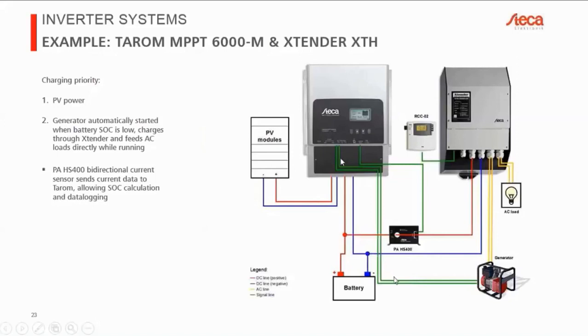Now, this generator can either be controlled by the charge controller in this case, or you can also control it by the Xtender, regardless. Either one of the two can give the generator a signal to start running when the battery is low, for example. And then finally, we also have a current sensor in the system, which can measure up to 400 amps. The reason we have the current sensor is so that we can see how much energy is flowing into the inverter or is flowing back, because obviously when the generator is running and we're charging the battery, there's energy flowing back into the battery.